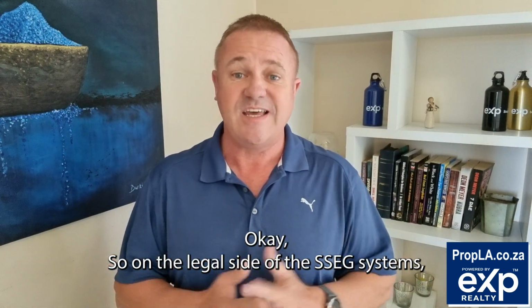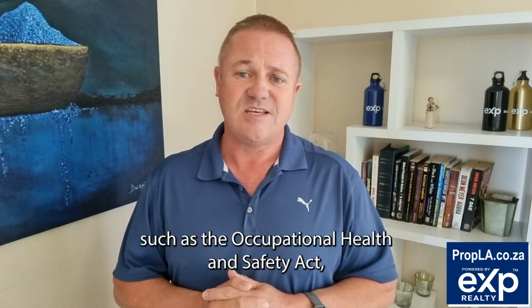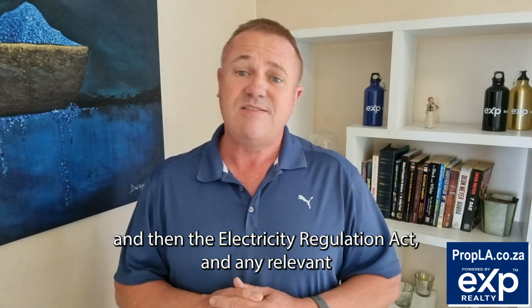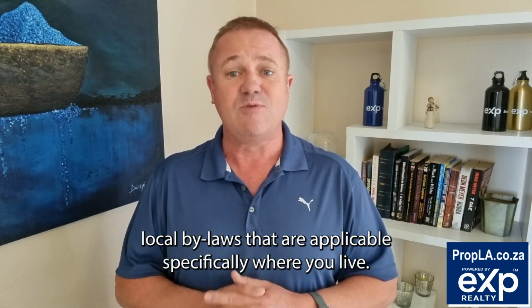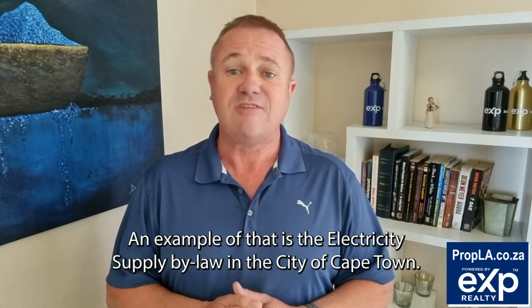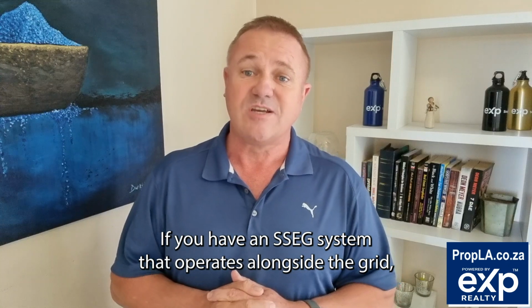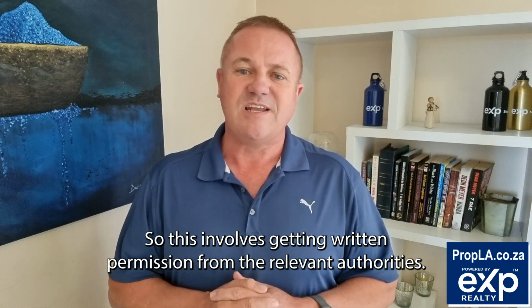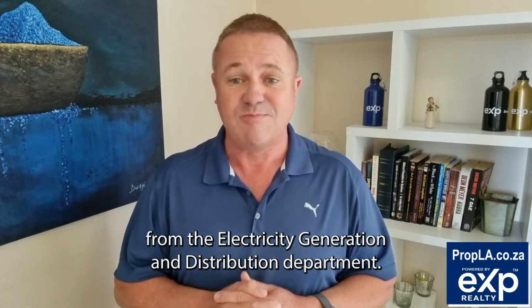Okay, so on the legal side of the SSEG systems, there are various regulations that you need to be aware of, such as the Occupational Health and Safety Act, also the Electrical Installation Regulations, and then the Electricity Regulation Act, and any relevant local bylaws that are applicable specifically where you live. An example of that is the Electricity Supply Bylaw in the city of Cape Town. If you have an SSEG system that operates alongside the grid, it must be approved and properly registered. So this involves getting written permission from the relevant authorities. As an example, in Cape Town, you need written permission from the Electricity Generation and Distribution Department.